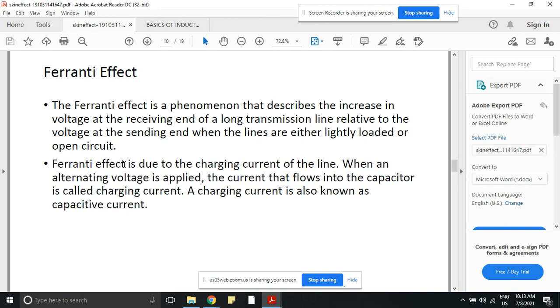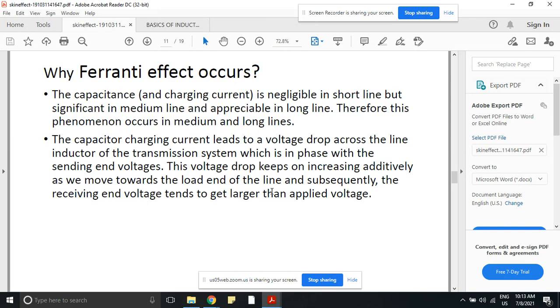The reason for the Ferranti effect is the consideration of the capacitance effect between the line and the return path of the earth. Because of the charging current of the line, this effect is added in series to the receiving end voltage, because the sending end voltage is no longer equal to Vr plus Vz, where Vz is the drop across the impedance. In this case, the direction of this charging current will be from the earth to the line. Hence, this charging current is added in series, aiding the receiving end voltage. Therefore, both the vectors will be added, and hence you get the additive value of the receiving end voltage. Hence, the receiving end voltage now becomes greater than the sending end voltage.